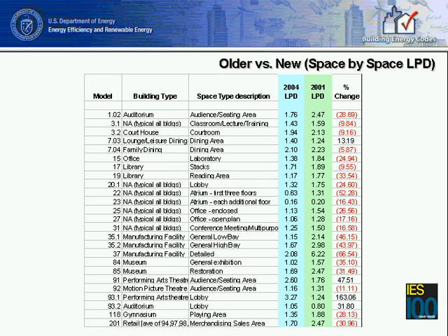Going on to look at what the results of that are, we have a comparison here between the previous version, 2001 ASHRAE in this case, and the 2004 ASHRAE. And as you can see in this percent change column, most of the values did go down. There was a tightening, if you will, of the requirements. But again, that's just based on a refreshment of all the different model inputs. These are the values that you will see in the standard. This is an example of approximately 25 of the 100 or so models that were actually created, and you will see a selection of these in the standard.